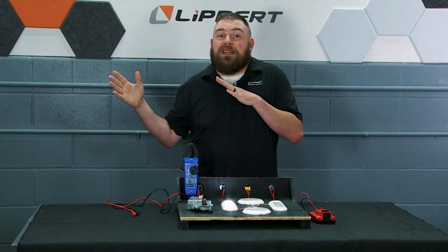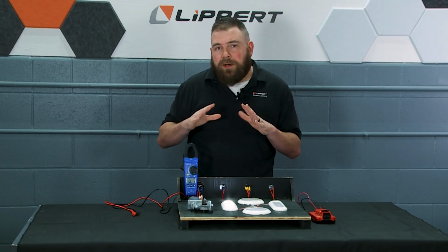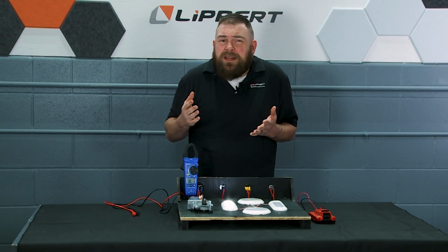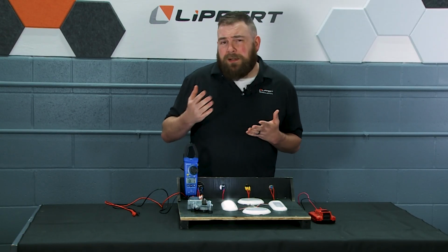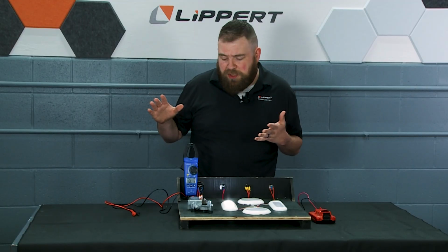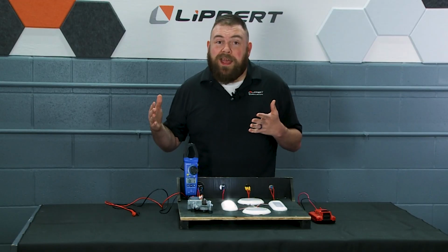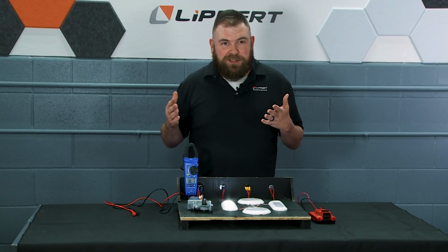If you have a very low number when measuring ohms, it means we have a very low resistance. And for things like wires or for things like a light switch, this is going to indicate that energy is capable of passing through it freely, or a ground signal, whatever the case might be. If your meter has a very high resistance, maybe it could indicate that there's some sort of damage and we'd need a little bit more investigation. If it has that OL, once again, this is open line. This is no continuity, and then we would replace that switch.